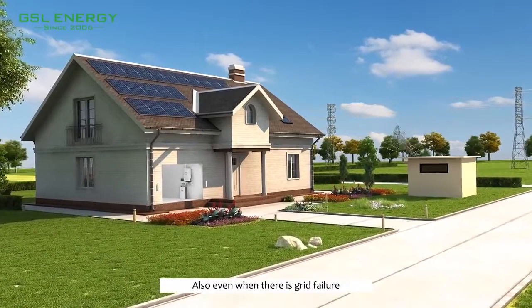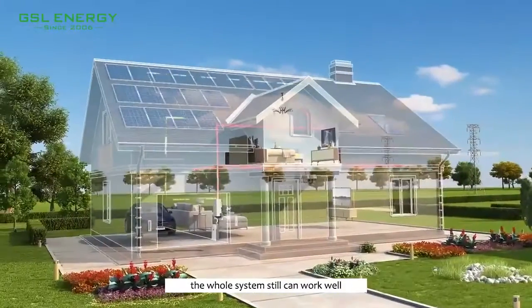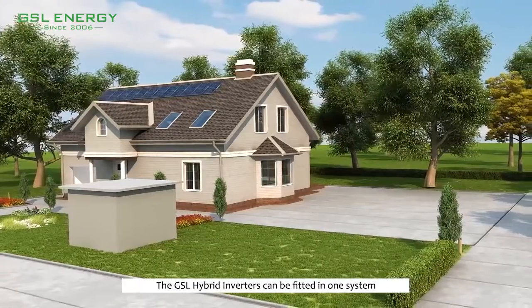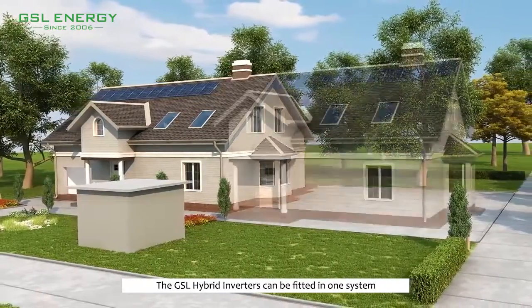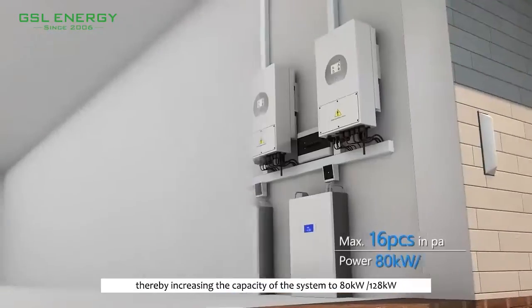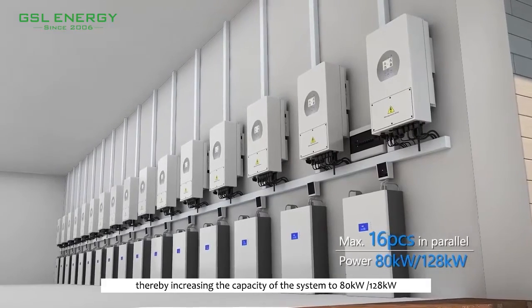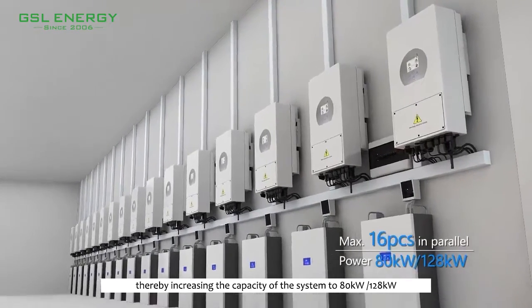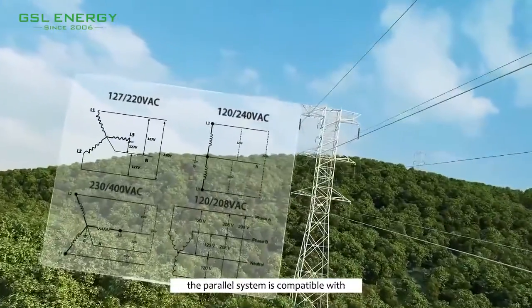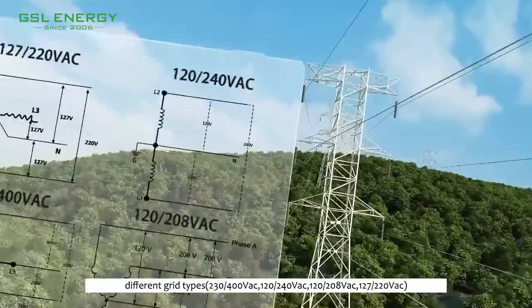Also, even when there is a grid failure, the whole system can still work well. The GSL hybrid inverters can be fitted in one system with up to a maximum of 16 units in parallel, thereby increasing the capacity of the system to 80 kW or 128 kW. The parallel system is also compatible with different grid types.